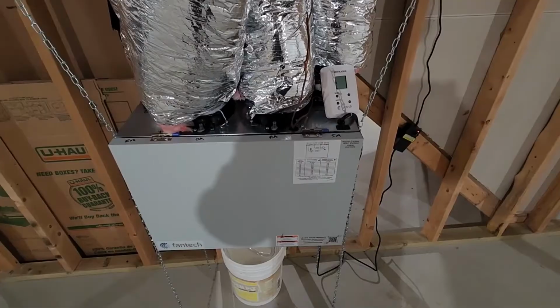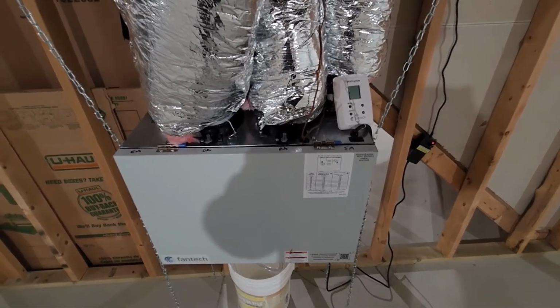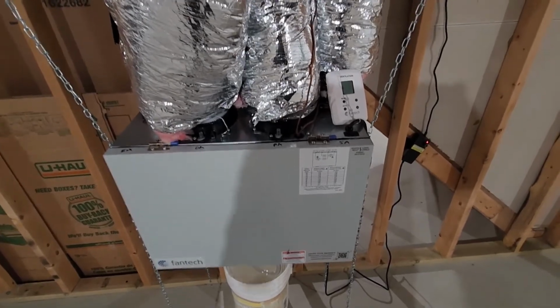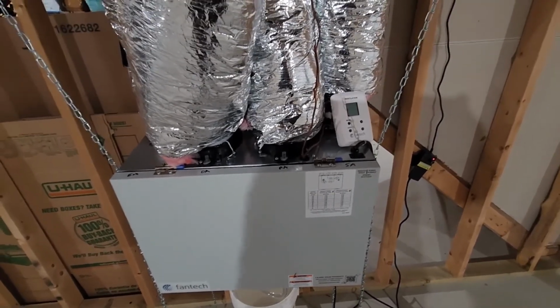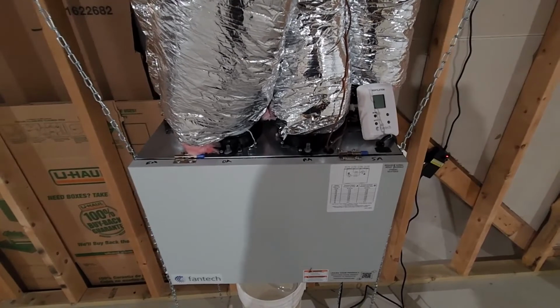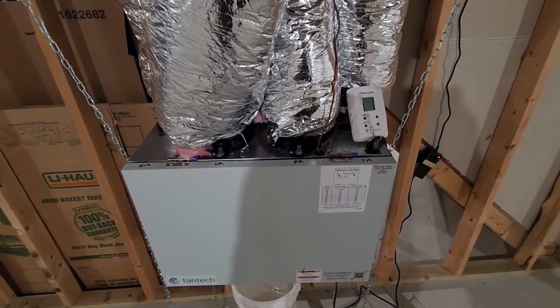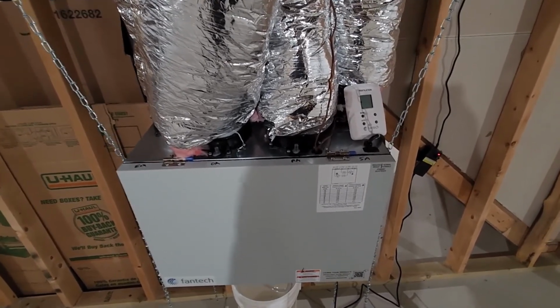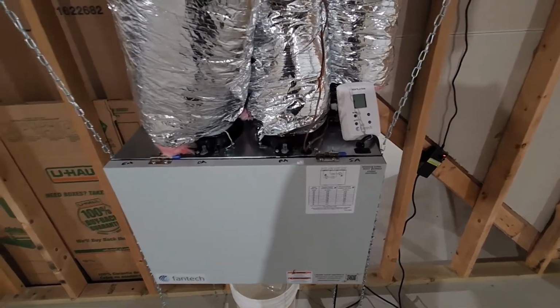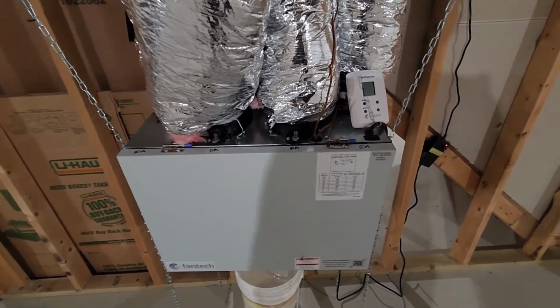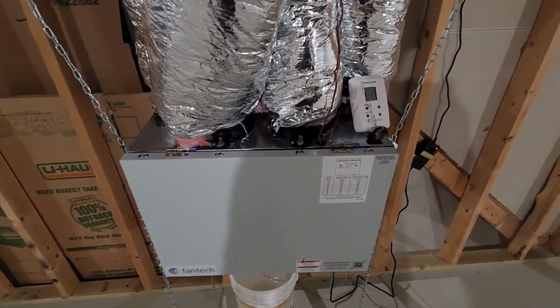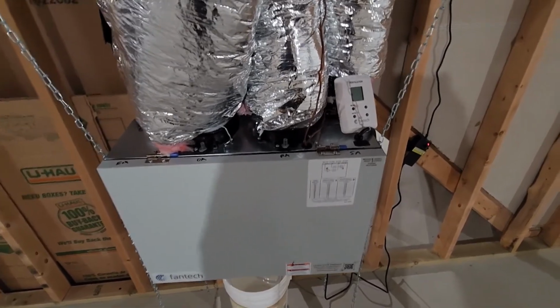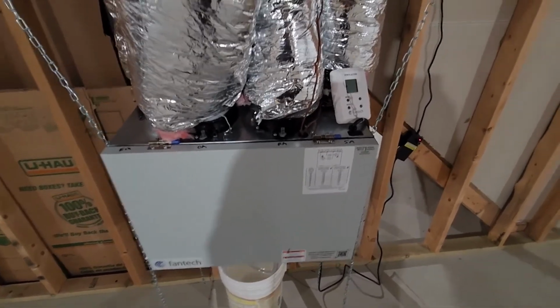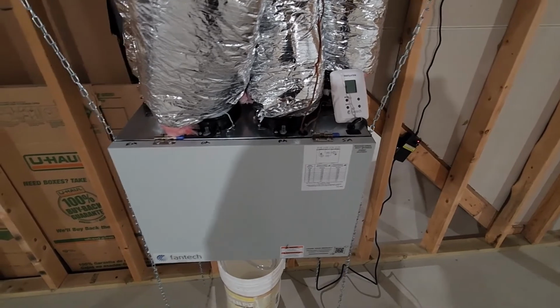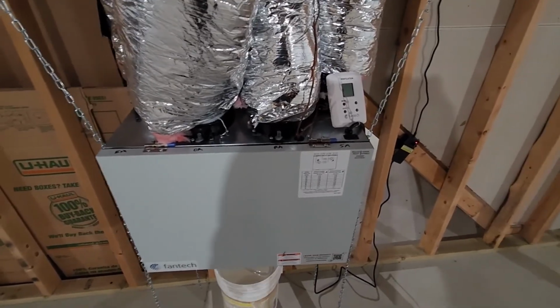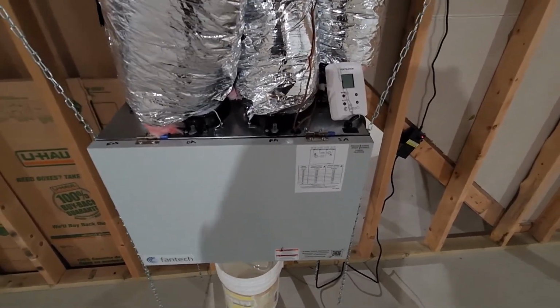So you want to keep the ERV well balanced such that it can maintain its full efficiency when you have an equal amount of air being brought in as you are exhausting. So that keeps your efficiency in that 60% range across all operating spectrums.